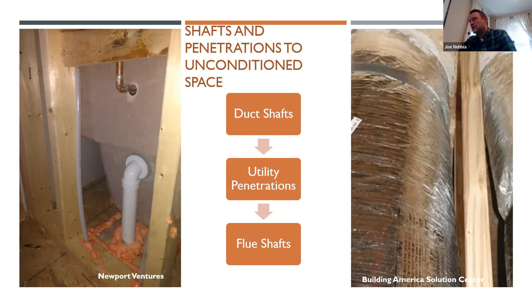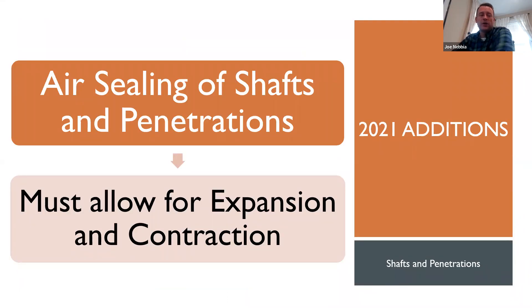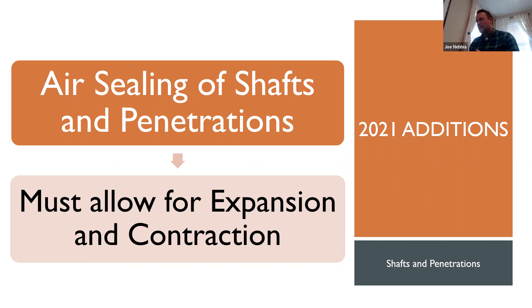Anywhere you've got a duct shaft penetration of any kind — for utilities, flues, pipes, or anything penetrating the thermal envelope — that has to be sealed. In addition in the 2021 IECC, that detail has to be sealed in a manner that allows for expansion and contraction. The code doesn't give much more detail than that, so it's a little vague. But the concept is that you can't use a sealing material that wouldn't allow for any expansion and contraction — if you've got pipes with hot and cold air going through, code says the sealing materials have to allow for expansion and contraction.